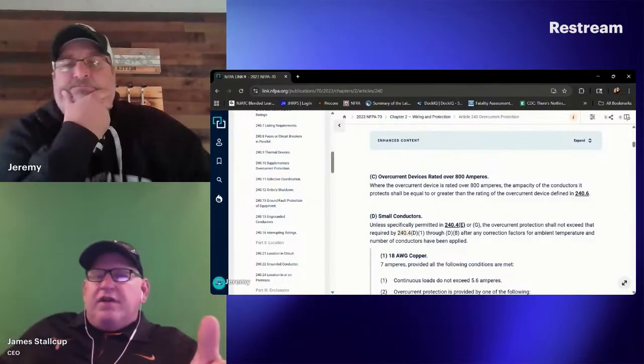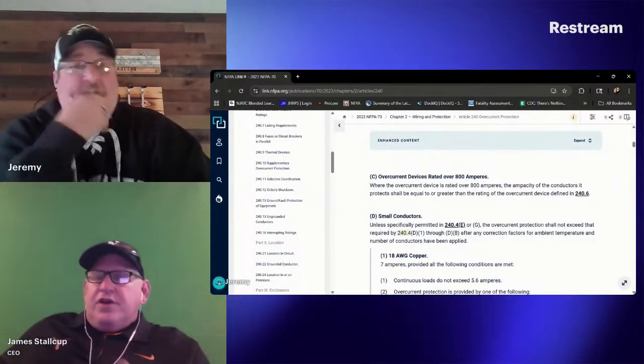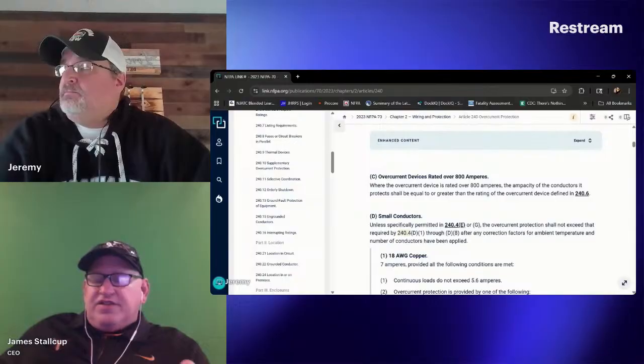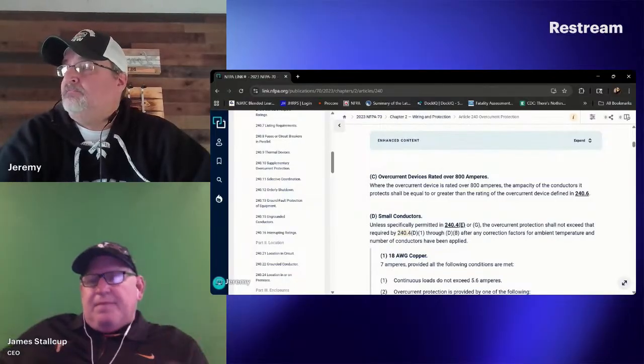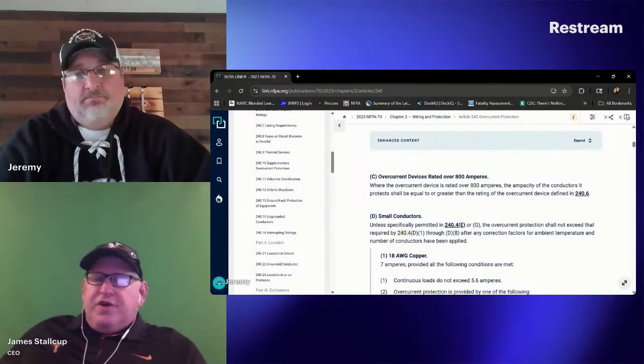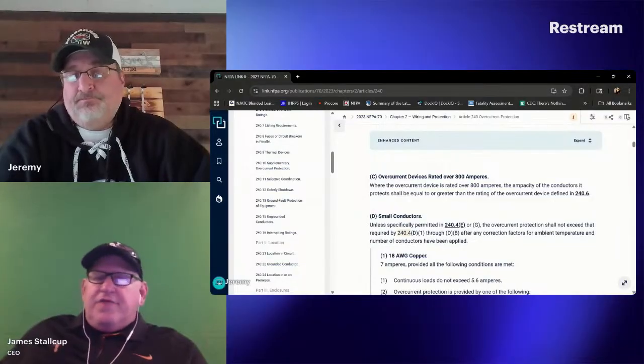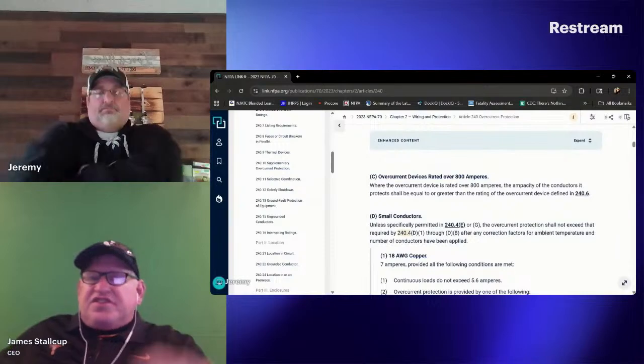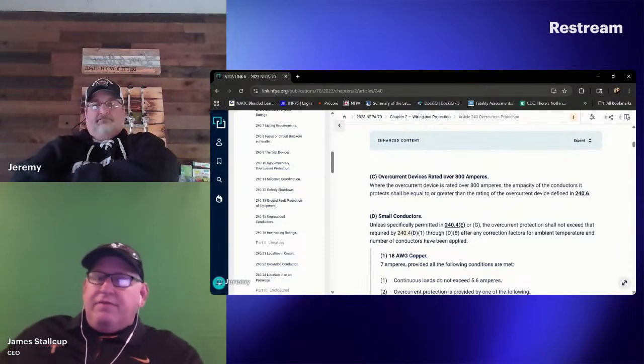You calculate a load of 905 amps. You go over to table 310.16. You pick up your 75-degree C column, come down, pick up 4/0. They're good for 230 amps. We paralleled it 4 times. That's 920 amps. Okay, my conductor size is set for the calculated load, right? Yep. You agree with that? Okay. So I've already set the conductors for it.